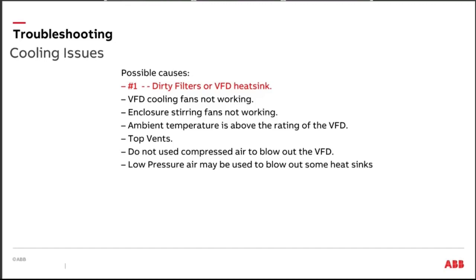Now, one of the things I want to caution you on, don't use compressed air to blow the drive cabinets out. You might be tempted, don't do it. Now, you might blow that drive cabinet out and step back and put your hands on your hip and say, look how nice and clean that is. No, it ain't clean. You just can't see the dirt no more. There's not a bit of difference in the world in flipping that kitchen rug back and sweeping all that mess underneath the rug and turning it back down. You don't see the dirt because you have blown the dirt and the debris behind the boards.